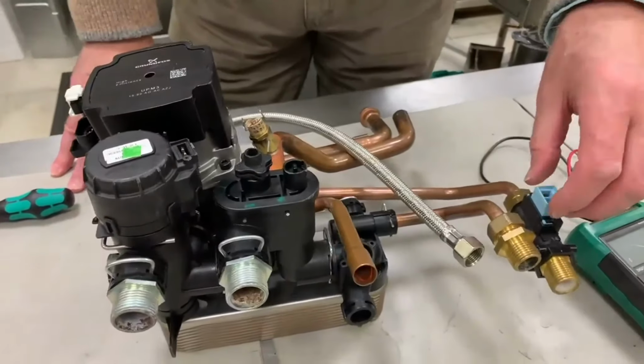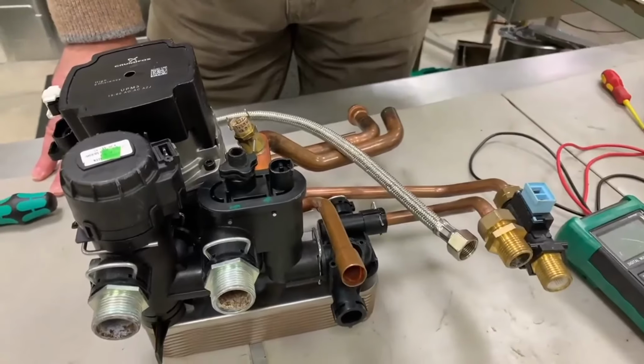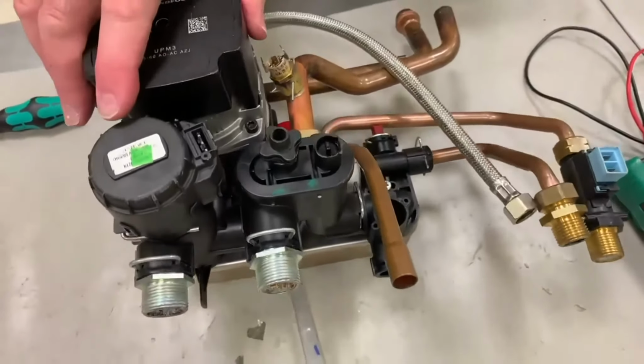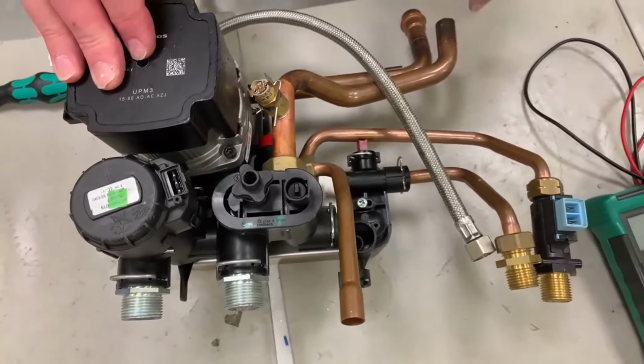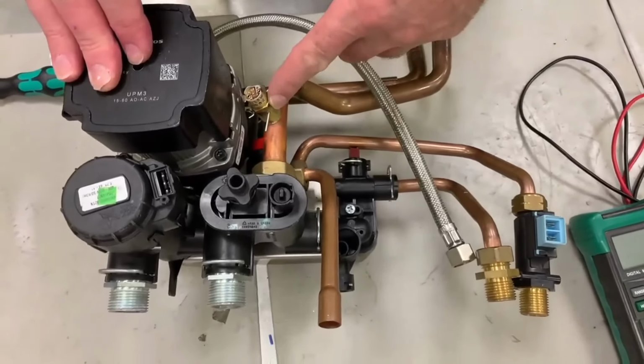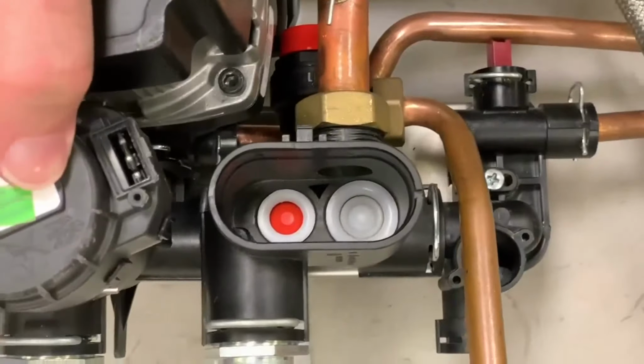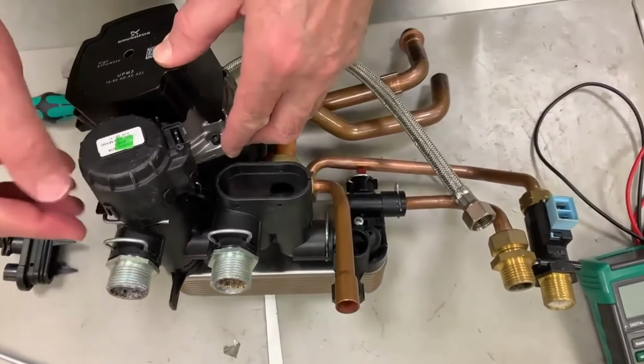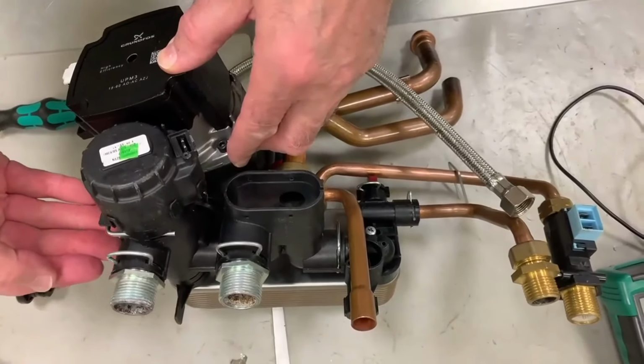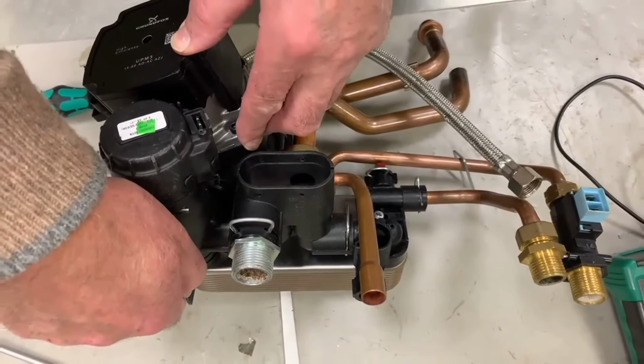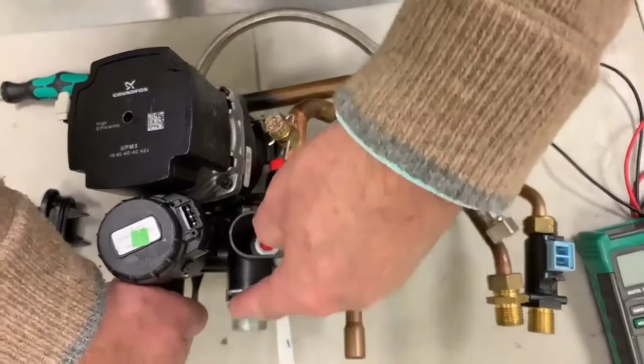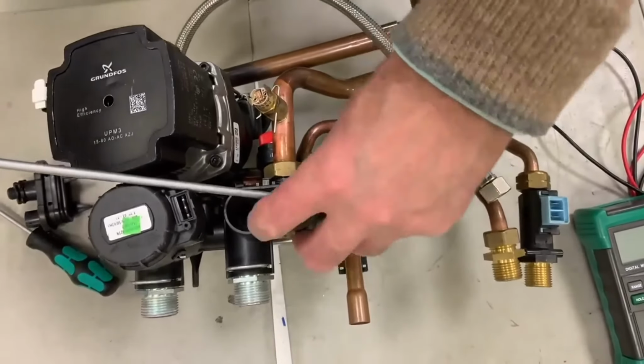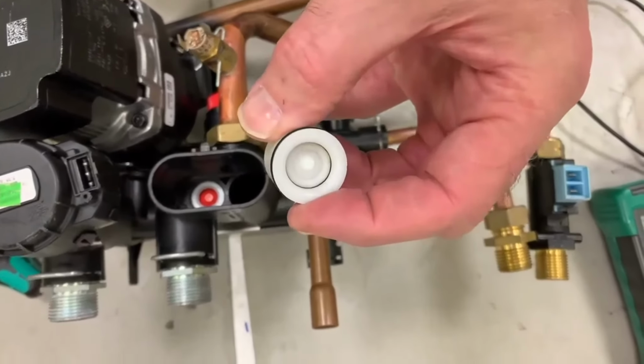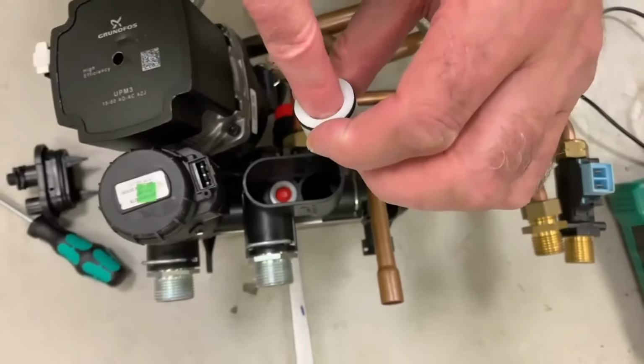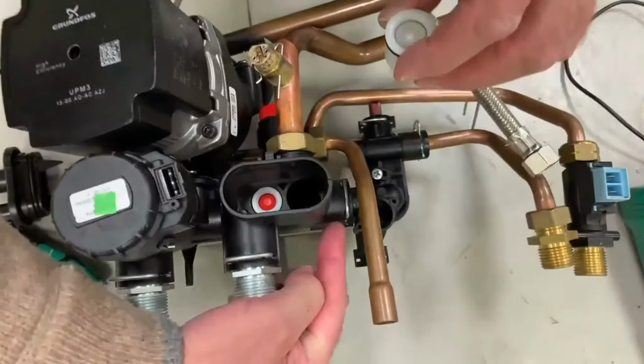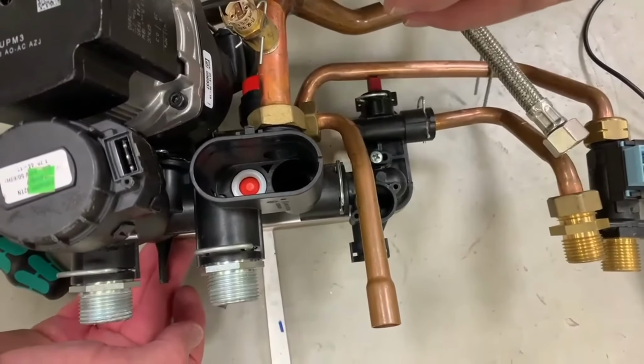The movement of water that is sensed by the flow switch or flow turbine has fired the main heat exchanger up here. The pump has kicked in. The pump is bringing down the primary flow from the main heat exchanger down this tube past the low pressure switch on this boiler. The flow passes into this chamber here. The diverter valve here has pulled up a cartridge here. This is the heating flow, that is the heating return. It's pulled up a cartridge and that cartridge has blocked the heating return. So the primary flow from the main heat exchanger can't go to the radiators. What it does, it's a very lightly sprung non-return valve. So the pump pushes the flow through that non-return valve there into the plate, warming up the domestic water passing through the other side of alternate plates.